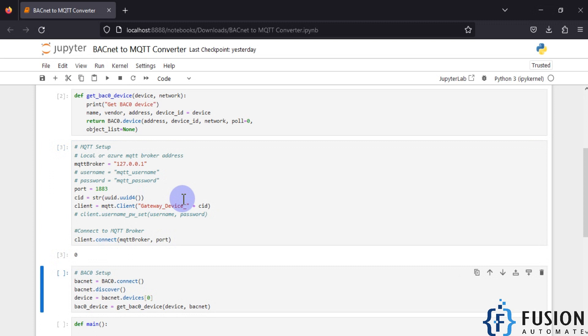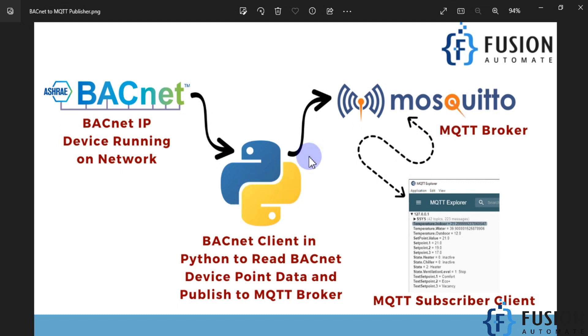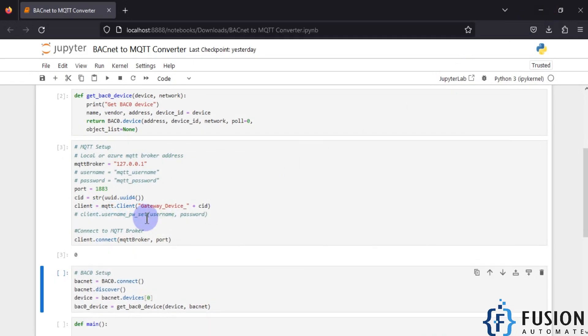In this case, our Python will act as two things: first as a BACnet client which can read data from our BACnet device, and also as an MQTT publisher — it will connect to our MQTT broker, publish data to it, and on the other side we have an MQTT client that can subscribe to those topics and get the recent values. Our Python is now connected to the Mosquitto broker.